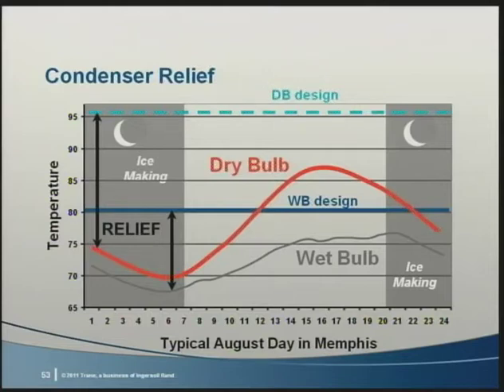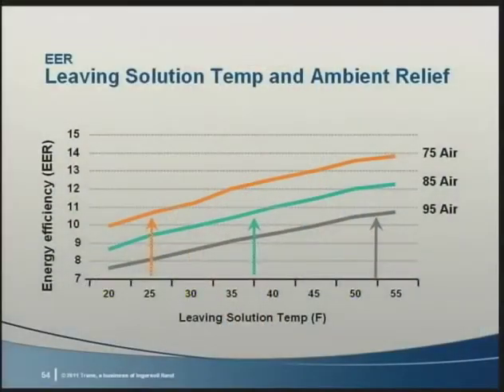This graph shows the difference between design ambient temperatures, both dry bulb and wet bulb, for a day in August. Note that the ambient relief for dry bulb is always more than the ambient relief for wet bulb. This difference in condenser relief is key to understanding that air-cooled ice systems perform efficiently during the ice build mode. An air-cooled chiller can make ice at night with better efficiency than that same air-cooled chiller makes chilled water during a design day. This slide shows that an air-cooled chiller in ice-making mode still has a slightly higher energy efficiency ratio than the same chiller on a design day making 45 or even 50-degree solution. This is due to the condenser ambient relief from 95-degree daytime temperatures to 75-degree nighttime temperatures when ice is being made.